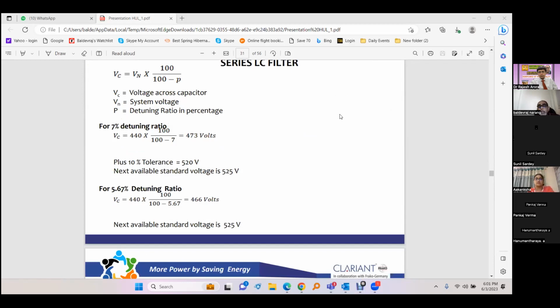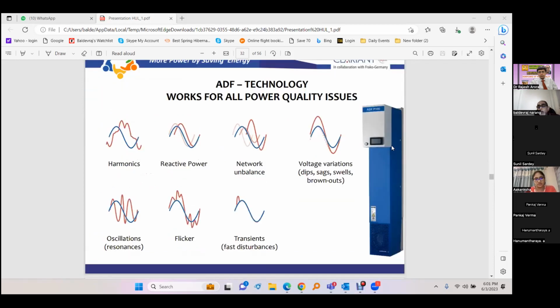So now we come to the active filter. Active filter, STATCOM, SVG or static var generator, or the grid inverter, they are all the same item. There is no difference between them. Only the application is different. So this can be used for harmonic correction when we generate harmonics 180 degrees out of phase with the harmonic frequency. That harmonic is cancelled. So we can cancel any harmonic, 5th, 7th, 11th, whatever is there in the system. We can configure it to that, and that harmonic can be cancelled out.